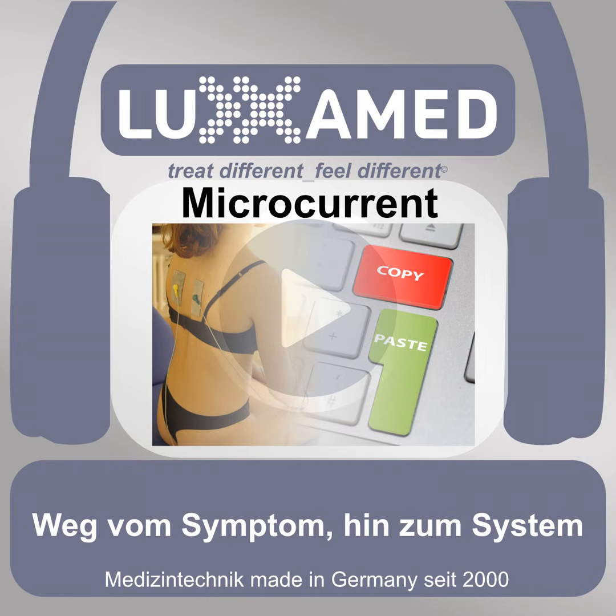It is important to know if you as a practitioner are involved in the circuit with bare hands, if you use it as a practitioner. Of course, because you are holding an electrode in your hand while working manually. Therapeutically, of course, that is harmless, but you are, after all, included in the circuit. You can, of course, solve that simply with classic disposable latex gloves. From a hygienic point of view, however, it should be borne in mind here that such textile electrodes, unlike the adhesive electrodes, fundamentally must be cleaned before they are used on the next patient. That should, of course, be taken into account.